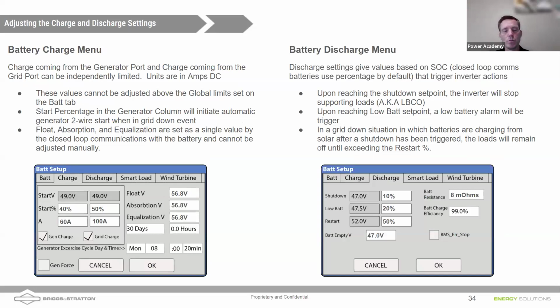And so it needs to use the hardware on the inverter, which is limited to 12K, as Daniel just mentioned, to go between battery and AC, DC and AC. All right, on the battery charge menu, so if you do have AC coupled solar come in, you will use the column on the left for generator charging. That's actually the gen port, also known as the smart load port on a Solark, and you're bringing your AC coupled through that gen port.